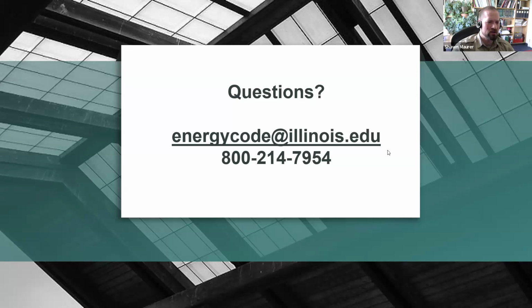Are the new requirements for process equipment for data rooms changing the intent of the energy code to control for comfort, cooling, or heating? The new definitions added into the code were to specifically designate what is an equipment room, what is a data closet, what is a data center, as far as those different space types. For data centers, there are requirements now for equipment efficiency and sizing, which is why those definitions were added to the code. So there's a different procedure to size the equipment for a data center, and there are specific efficiency requirements for the equipment serving data centers. That was added into the code.